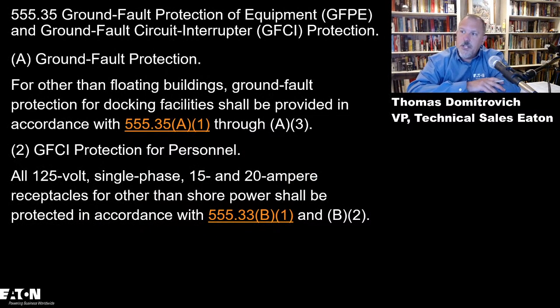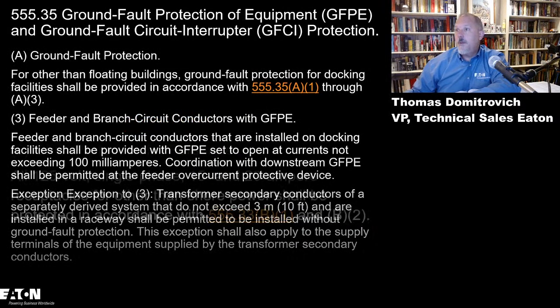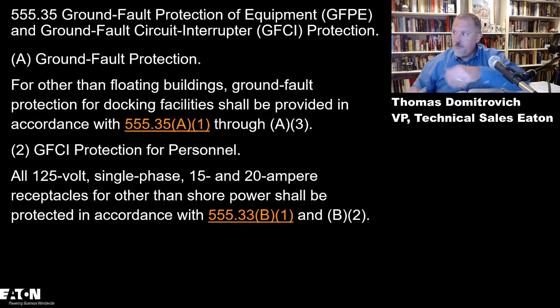GFCI protection for personnel. All 125-volt single-phase 15 and 20 amp receptacles shall be protected in accordance with 555.33 B1 and B2. So let's take a look at B1 and B2. I'm going to read that to you because I'm not going to go bouncing back and forth. 555.33 B1 and B2. That says GFCI protection for personnel, receptacles in other locations shall be protected in accordance with 210.8.